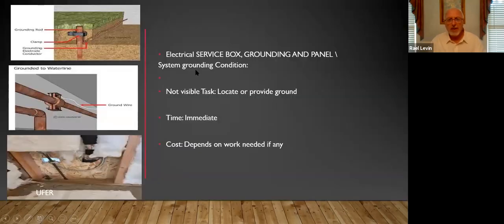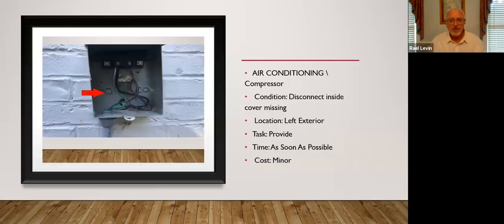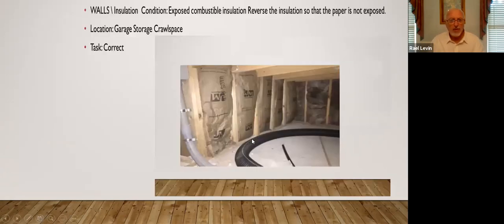Just a quick look into the electrical service. We're looking at the grounding, different types of grounding rods, perhaps metal to copper if there's copper water supply. The most common these days is a UFER ground, metal driven into the foundation when it's poured, then connected to the home for proper grounding of the electrical system. Sometimes there are just missing panels meant to prevent us from sticking our hands inside, and those should be installed.